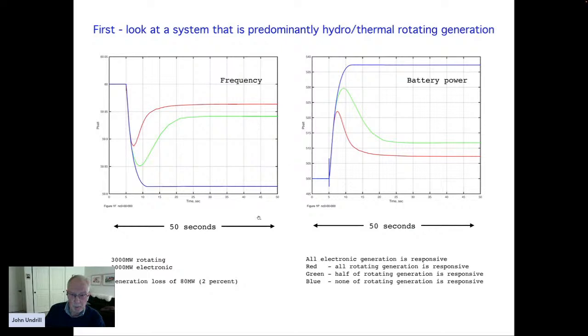bit lower. If the rotating generation did not contribute to regulation and left all the regulation to be done by the electronic generation, then the electronic generation would have to do all the response. So frequency would settle down here, and the response of the power of the electronic generation would go up here, and you'd still be able to do it. We've never seen that yet in any of the electric grids that I'm familiar with. Perhaps on shipboard systems, which are a little bit specialized, it may have happened already, but you wouldn't want it to happen. You'd want to bring the frequency back up to where it should be, which would be perhaps somewhere between here and here.